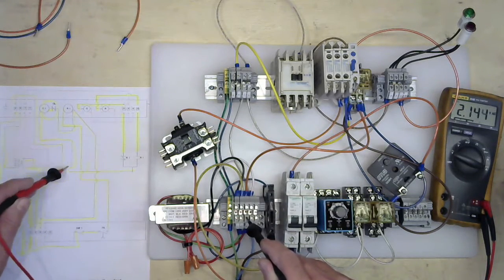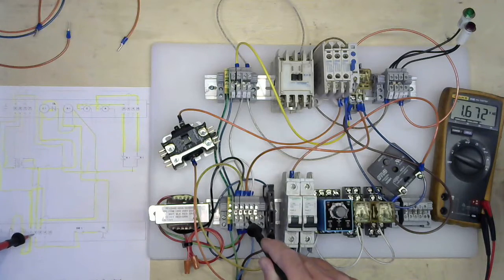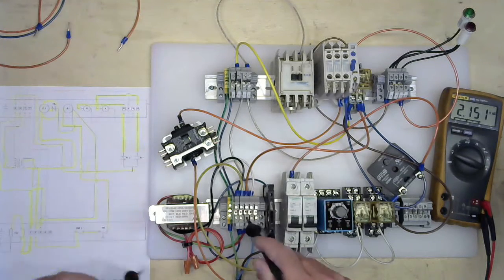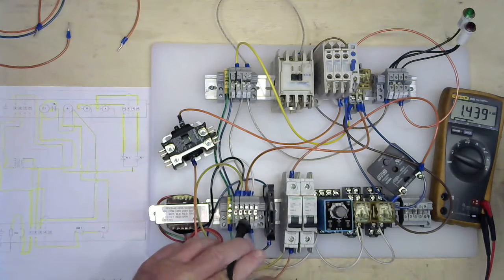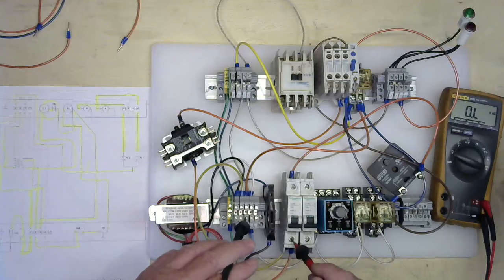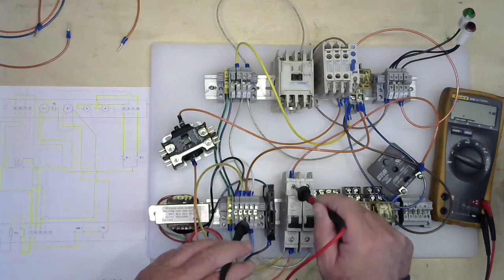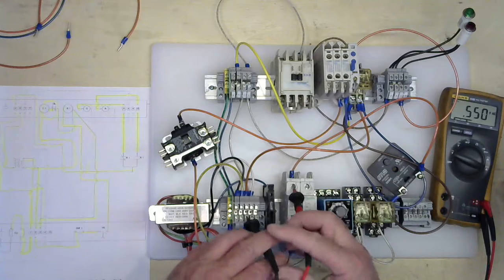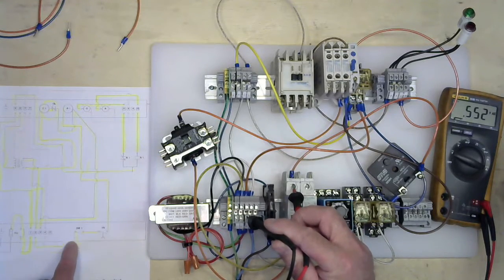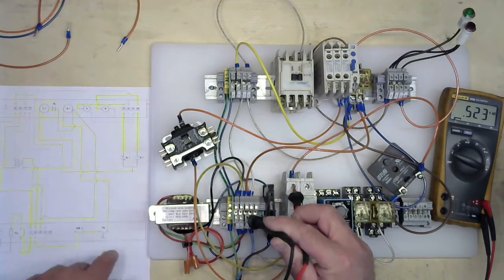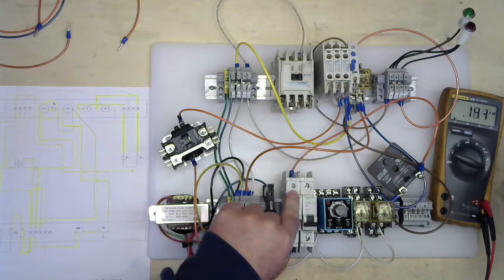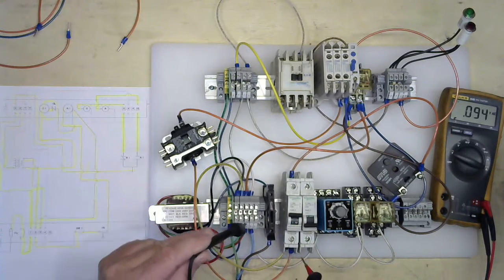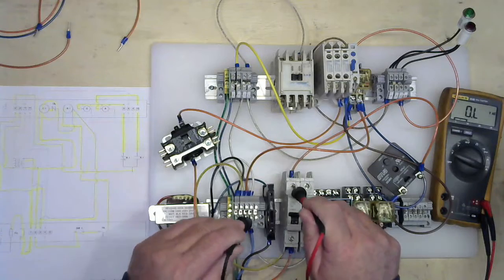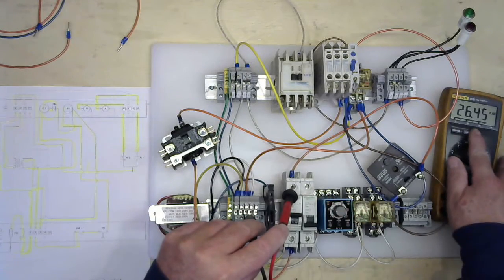If I follow my wire along here, C1 is always going to get power as long as I have power to my transformer. And then we should have power to the primary side of our switch here, which we do. If we check on the other side of the switch, we do not have power. So I have power to this point, I do not have power here. If I close my switch here, checking from 3 to my switch, it now has power.